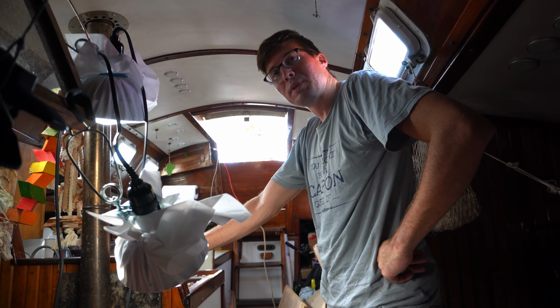Okay, I'm going to call them banks 1, 2, and 3, even though they're just all one giant bank of batteries. So what ended up happening is bank 1 and 2 are running, bank 3 is not for some reason. When I gunned it all the way, I was sucking in 180 amps before it cut out. The BMSs are only rated for 60 amps, so we went above the 120 amps from those 2 BMSs. 3 of them should have been able to do it.